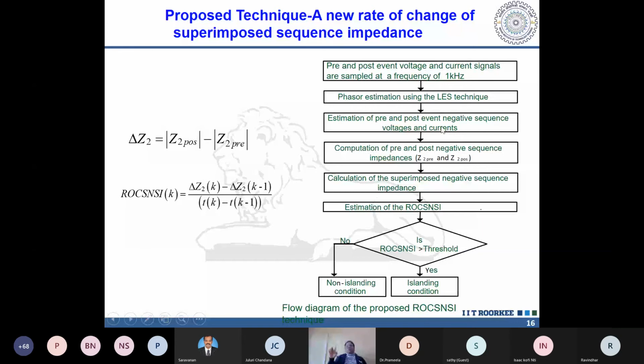After knowing V2 pre, I2 pre, V2 post and I2 post, we can easily calculate the ratio to get Z2 pre and Z2 post, and using this equation we calculate the superimposed impedance. Then we took one more parameter, the rate of change of superimposed negative sequence impedance. After delta Z2 is calculated, we calculate the subsequent change of delta Z2 with respect to subsequent change in time, known as the rate of change.